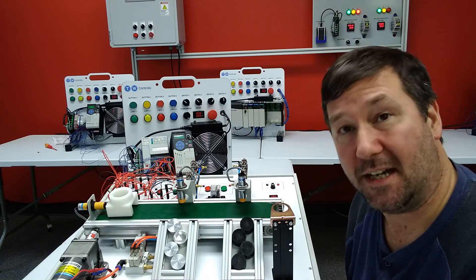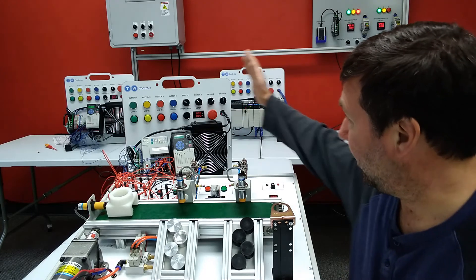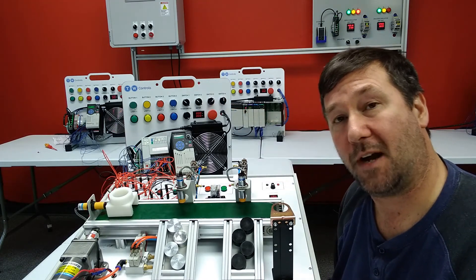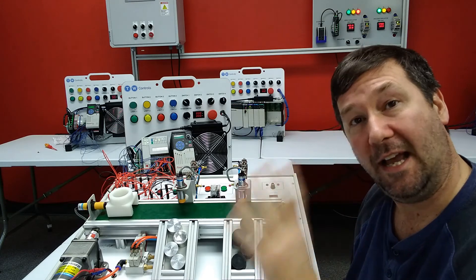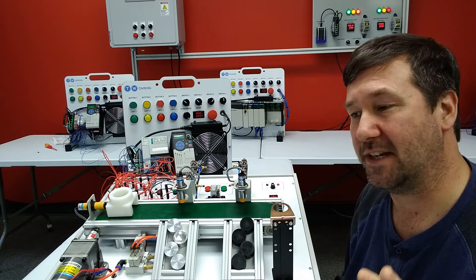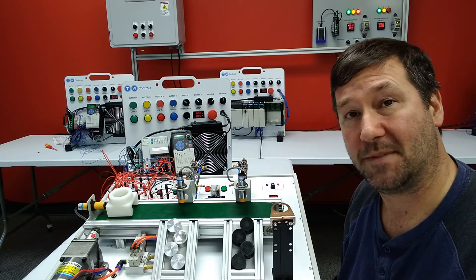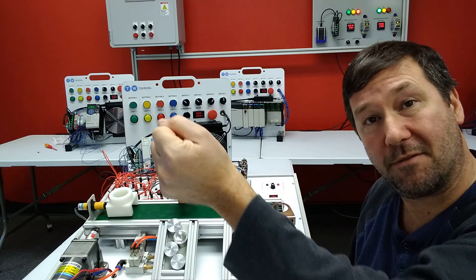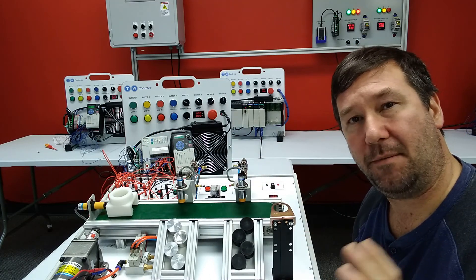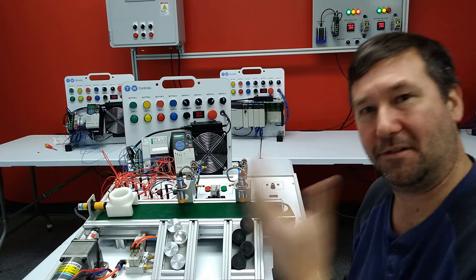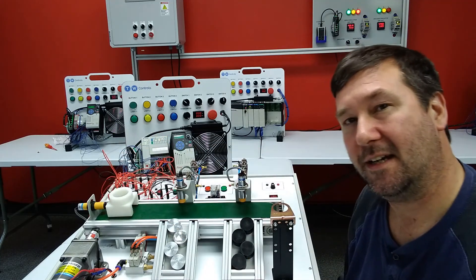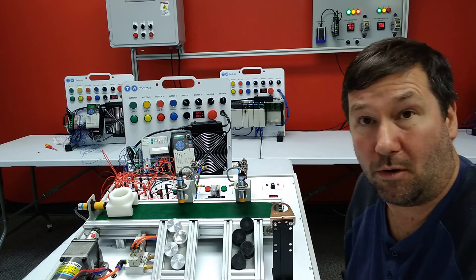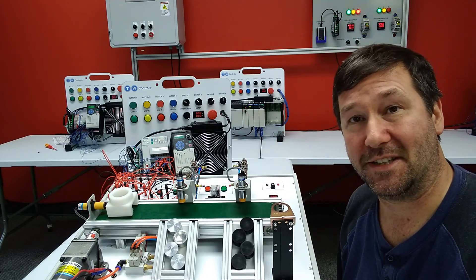So there's how to make an automatic control to start and stop your conveyor and also how to add a hand-off-auto switch. Now somebody in the comments will probably put that hand-off-auto switches should be hardwired and not go through the PLC. And honestly that's a discussion I don't want to get into in this video because there are times that I would absolutely agree. Hand-off-auto should be hardwired that way if your PLC is bad you can switch over there to hand. However with so many controls now where systems are so integrated and you know you don't just have a standalone conveyor that you may need to walk up and just do that you're seeing more and more that a lot of them are just on an HMI. So it just depends on your situation there.